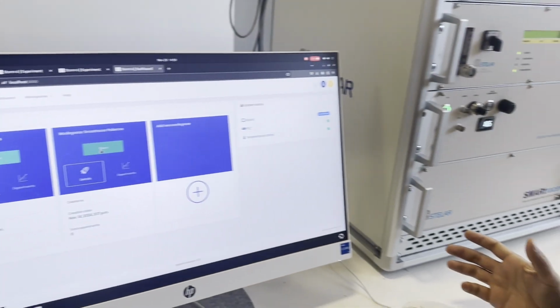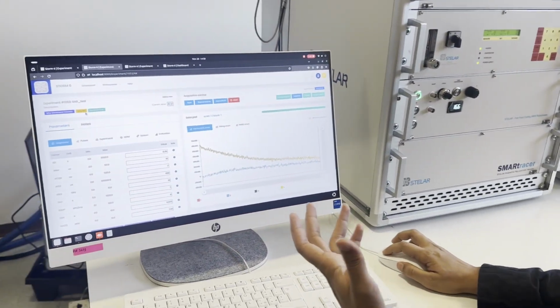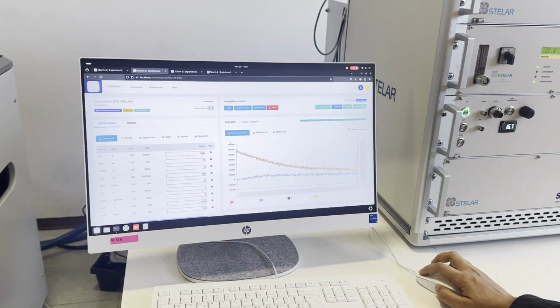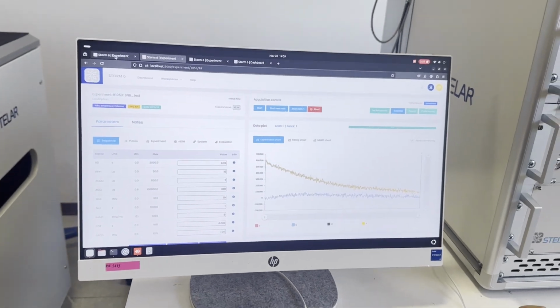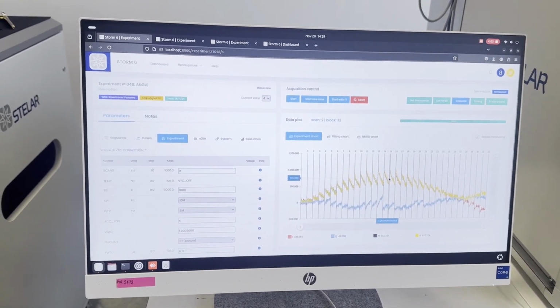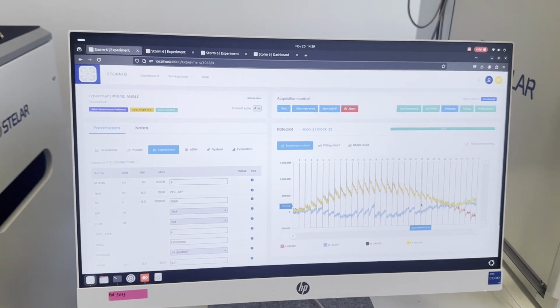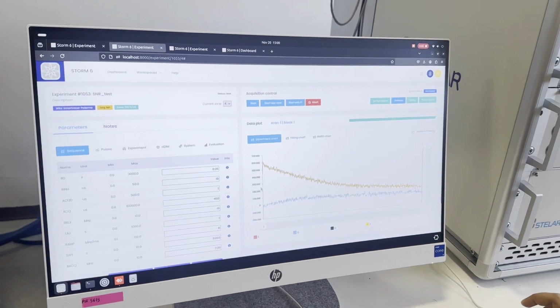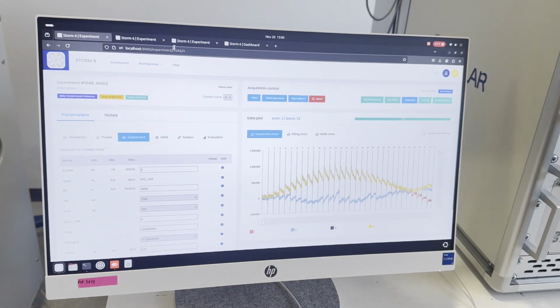In order to perform experiments, the best thing is to make sure that your instrument is in resonance. And to get resonance condition, you have to make sure all parameters are correct. Once those parameters are correct, then you can perform a simple experiment which we call non-polarized NP sequence. And the next step which we will do is to perform an angle sequence. From here, we will get the correct PW90 value of our instrument.